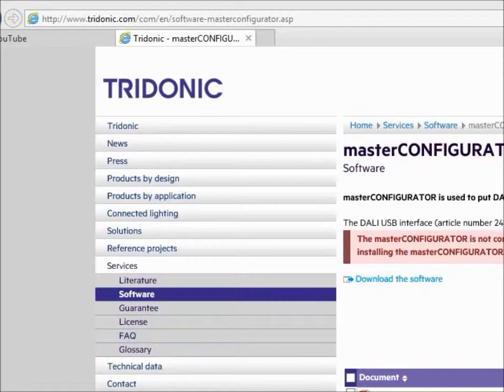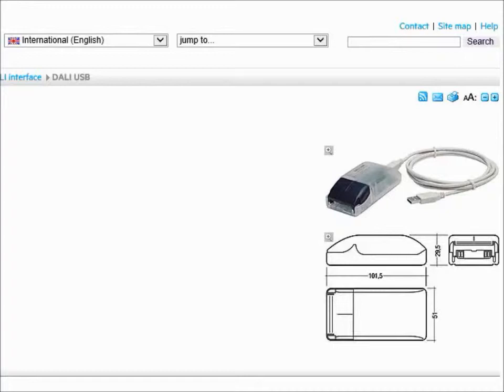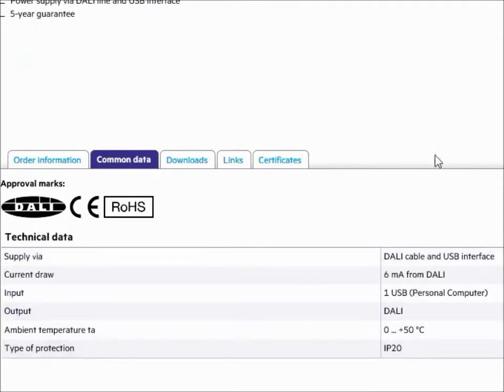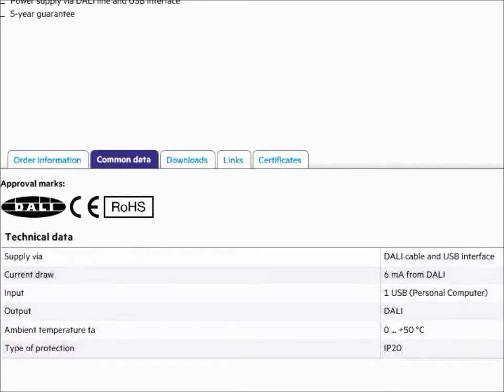You will need the DALI link that plugs into either a USB port or a serial port, and I'm sure you can find one on this site as well. I found the interface on their website by searching USB to DALI, and it came up with DALI USB — that's apparently the name of this product. Here is a brief description: power supply via DALI line and USB interface. So no external power supply is needed other than the USB port and the DALI bus supply. It takes 6 milliamps off the DALI bus supply to run, and it is a USB interface and works just great.